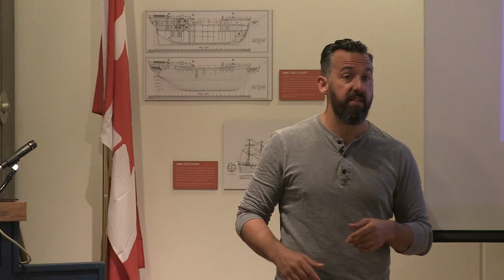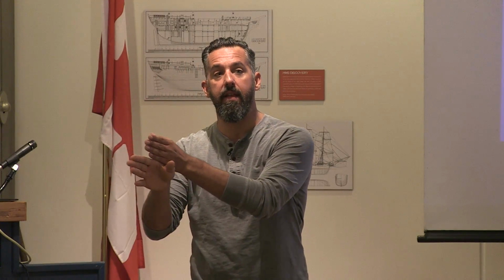And not fusing a wire, on some boats, it could be every single wire. You could have 50 circuits that are unfused, 20 circuits, 10 circuits. Every other new circuit is unfused. They put fuses in the wrong places. They think the fuse is only for the appliance. They fuse no wires, only the appliance. It is the Wild West for fusing on a boat and breakers. Or people think they have a large fuse at the beginning of the circuit and it protects their whole boat. I'll show a few videos when we get back after lunch.